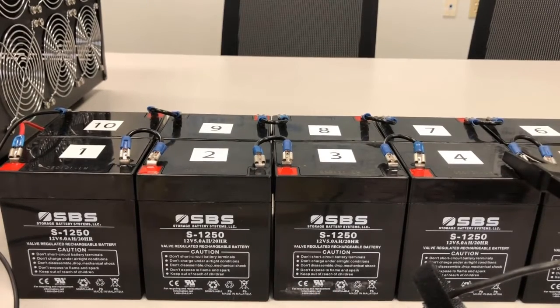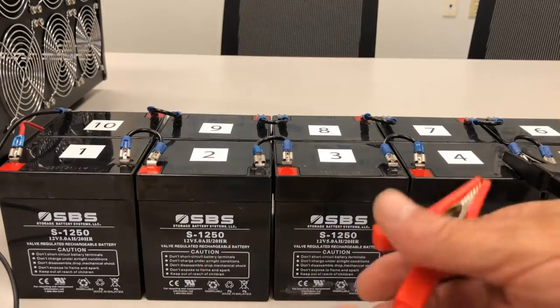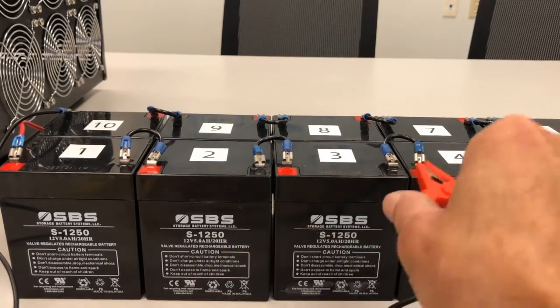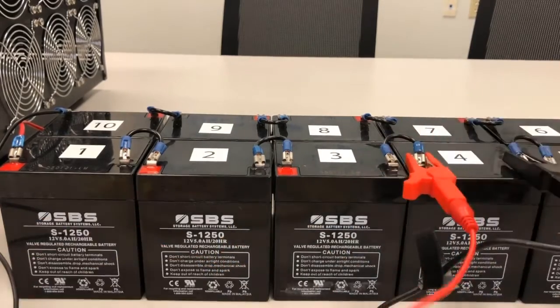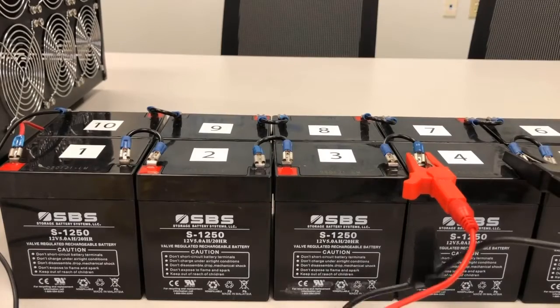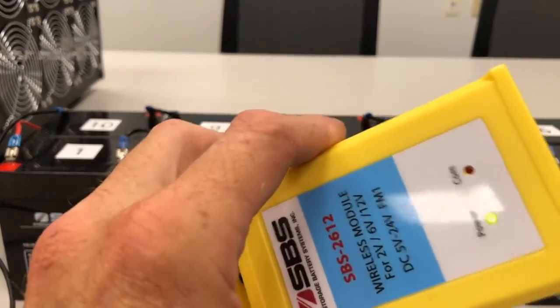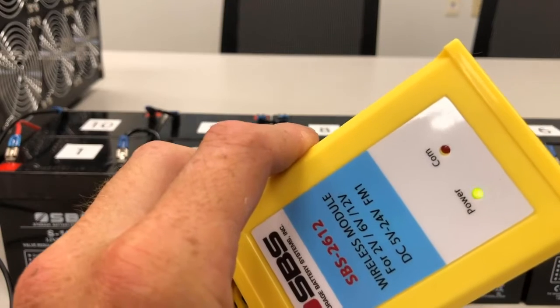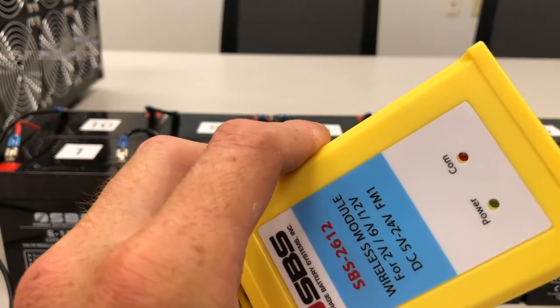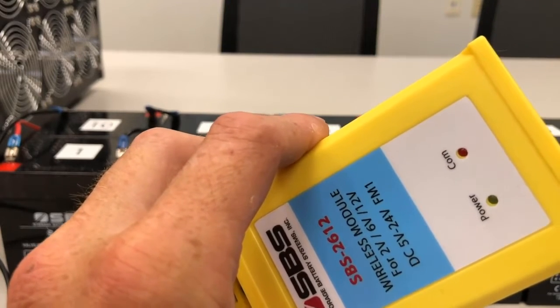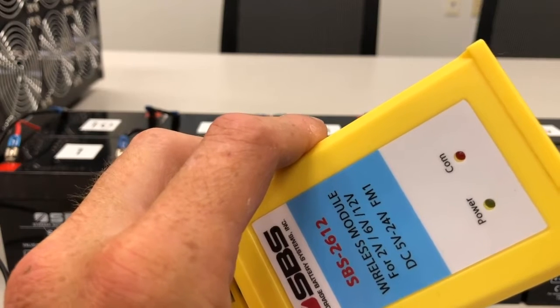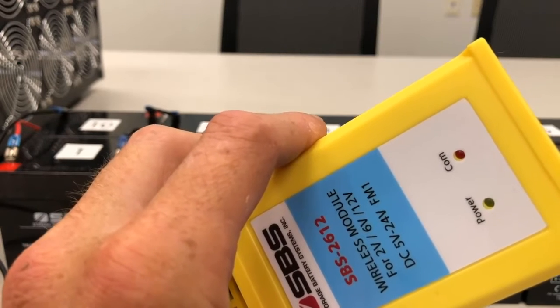In order to get the module to power up, the red lead is going to connect to the positive post of battery number 4. As soon as those two leads are connected, you'll see the LEDs: the green power light flashing, indicating that the module is powered up, and the red LED flashing, indicating that the module is communicating to the load bank.